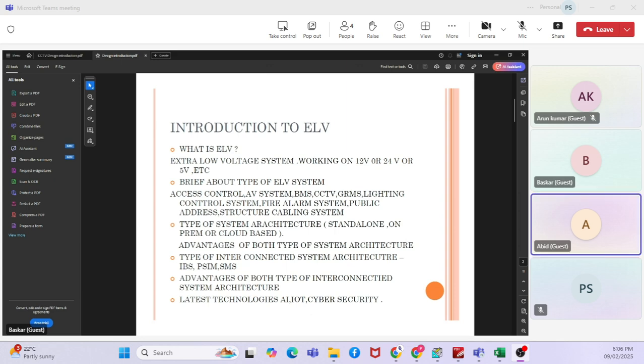Yeah. Zone-wise alarms will be given to the access control system. For example, if fire occurs, not all the doors open, right? Not all the exit doors. That's why we define compartments or zones in the fire alarm system. When we define the compartments or zones and fire occurs, there will be a sequence. Within that fire zone, within the fire compartment, whatever fail-safe doors there are have to open so the people can evacuate. It's like a big architecture. Not all the doors have to open, right?